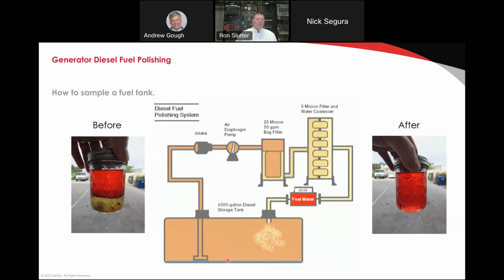And so there's only a little triangle on each corner of the plate that holds up the weight of the generator that allows the fuel to mix between these different segments. So if you only have one input port or output port here, and you're only able to clean it through that, you're only hitting one of the segments of the tank. So it's important when you buy a diesel fuel generator to have two ports.